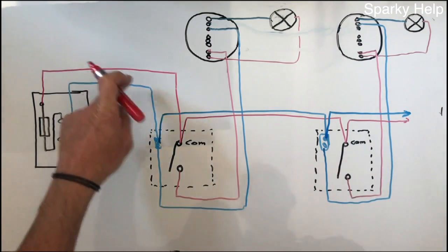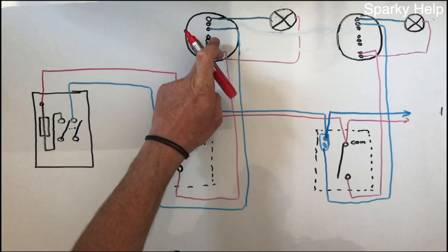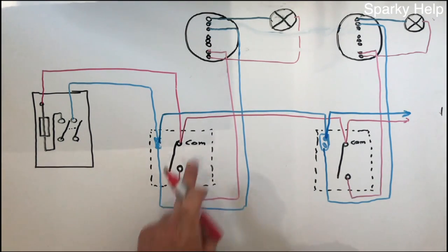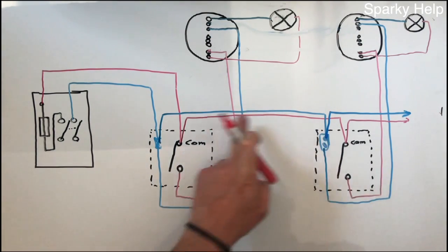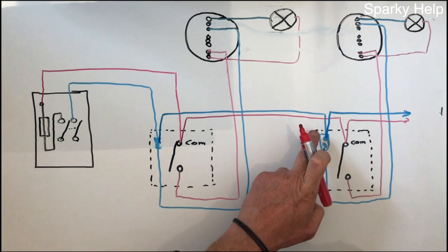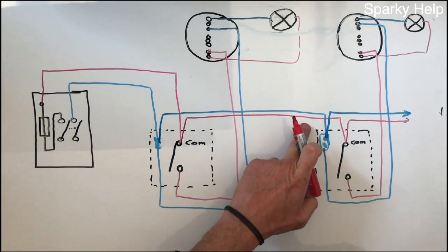So we have a twin and earth cable coming in, a twin and earth cable coming up to the light, this one you would mark. Twin and earth cable linking to provide power to the next set of lights, don't need to mark this one because we know what it's going to do.